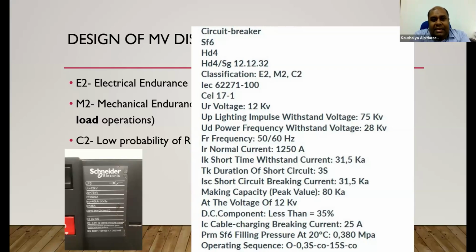Lightning impulse 75. These are the nameplate values. Operation frequency 50 or 60. Nominal current 1250 amperes. Short circuit withstand current 31.5 and duration 3 seconds. This is not the internal arc classification. This is the arc rating or the short circuit withstand current for the particular circuit breaker. This does not apply to the whole switchgear system or the whole secondary distribution system. So don't be fooled by seeing 3 seconds. Your distribution system will not have the internal arc classification for 3 seconds. The breaker or the switchgear will have. And so on. There are so many things they have given.